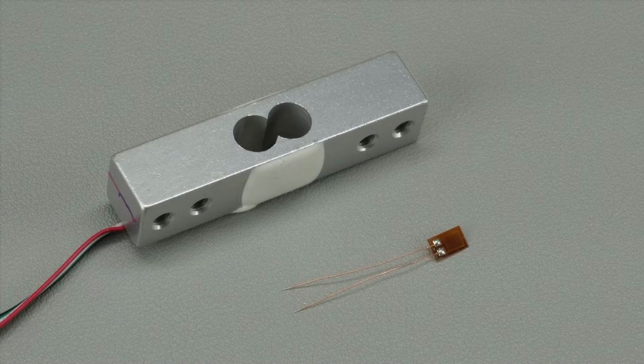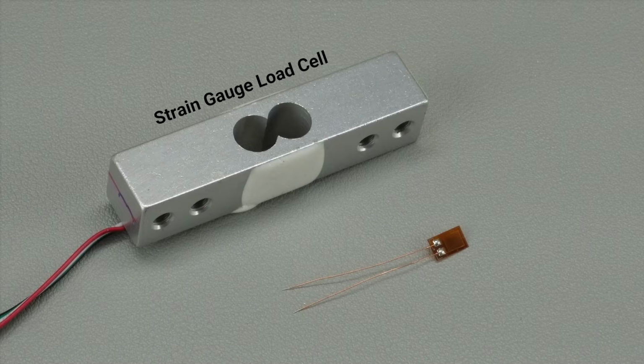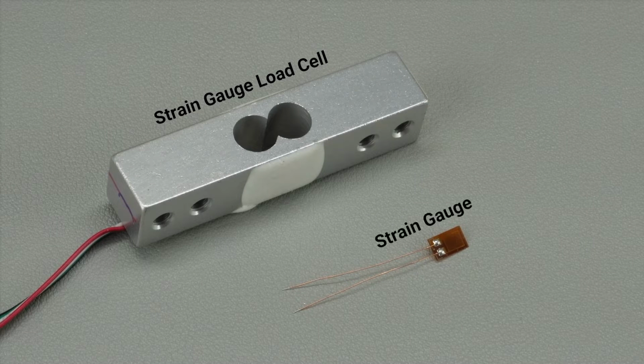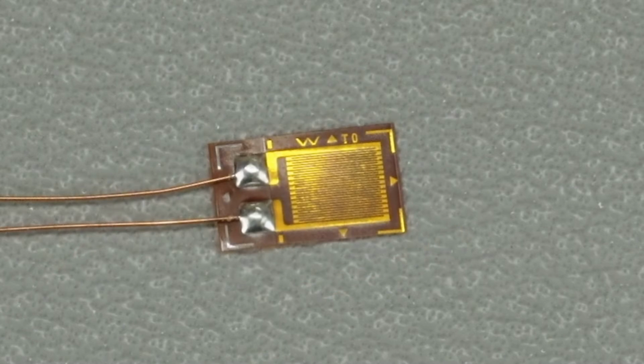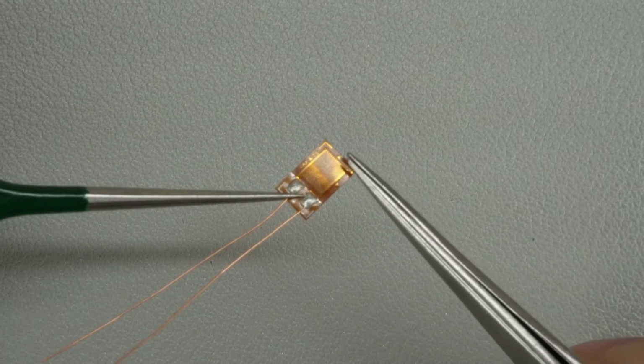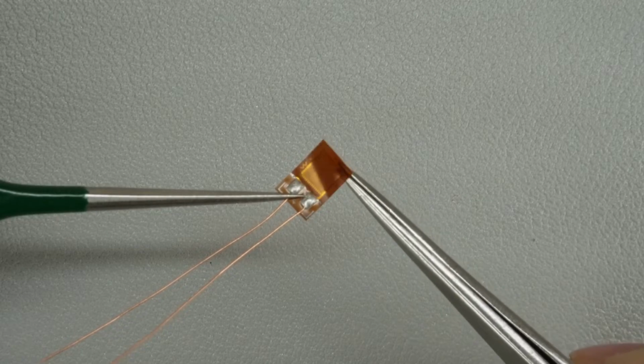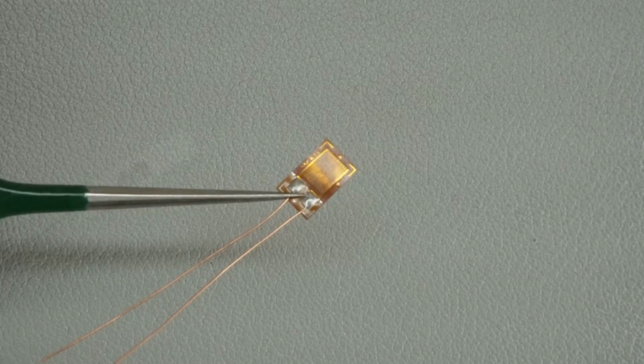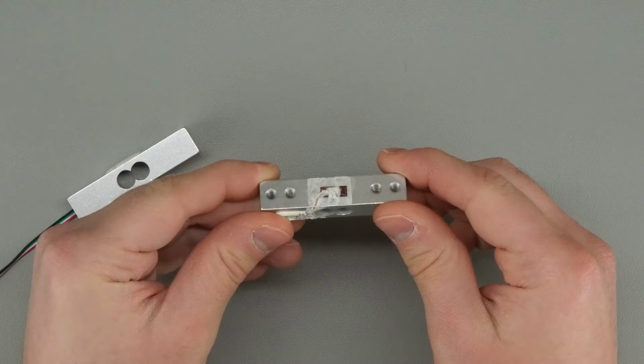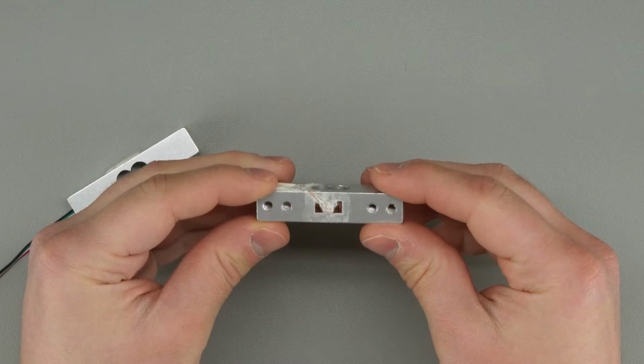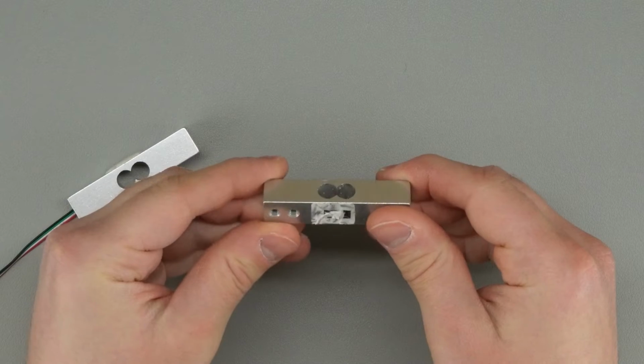Strain gauge load cells, like this one here, use small, resistive sensors called strain gauges to convert mechanical energy into an electrical signal. A strain gauge typically consists of a fine metal conductor that's arranged in a specific pattern and is attached to a thin, flexible, non-conductive backing. As the strain gauge experiences tension or compression, the resistance of the strain gauge changes. The strain gauges are glued to the frame of the load cell, and a protective coating is then applied to them. Here, we can see the strain gauges exposed.